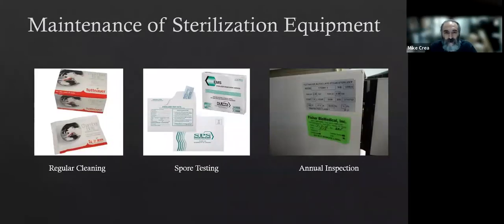You are going to have to maintain your sterilization equipment, so you have regular cleaning. Every autoclave has its own brand of full system clean. So Tuttnauer will have a Tuttnauer clean, Pelton & Crane has a Pelton & Crane clean. You have to make sure you're using the correct autoclave cleaner for the autoclave that you're using. If you use the wrong product to clean the autoclave, you can have a problem and you can really damage your autoclave.